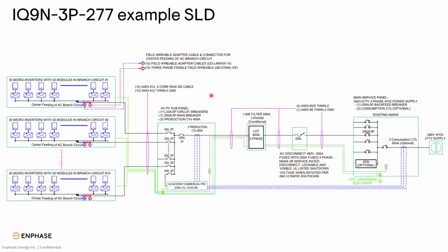Next, we have a line filter. That is an optional thing. You're only going to need a line filter in one of two areas. One is if you have a project that has significant line noise in the building. That can stem from large electrical motors or medical equipment, which can cause disruption and line noise that can mess with the gateway and how it communicates with the microinverters. So in this example, we have one gateway and a line filter, so we're going to assume that there's heavy line noise and that we want to make sure we don't have any communication issues.